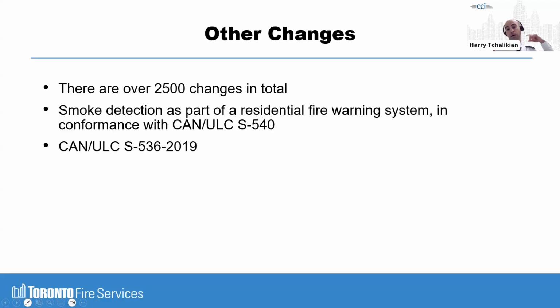And very importantly, be mindful that there is now a new CAN/ULC S536. We're now into the 2019 edition. For your annual and monthly fire alarm system inspection, maintenance, and testing, it is approximately 30% more involved and has more requirements. So you are going to be getting an extensively larger report. Just be mindful that your annual inspection meets the 2019 standard, which is a significantly higher standard. If in doubt, give us a call. So that is our last slide in the presentation.